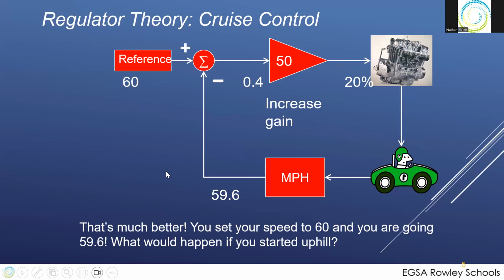So it actually starts to get unstable. You could actually get to the point where it becomes a natural resonant frequency, and that's where you speed up, you slow down, you speed up, you slow down. Full throttle, that's too much. Back it off. You might have seen this in your power regulators, your watts and your VARs swinging back and forth when you try to push too hard and get too much gain. Well, natural resonant frequency can also be a problem, right? Here's a good example.